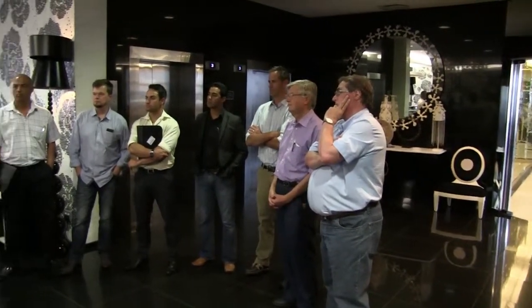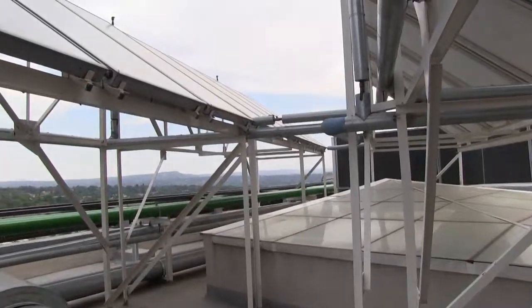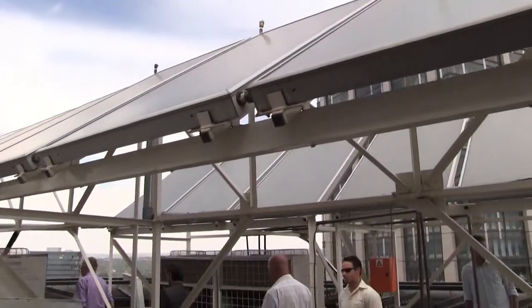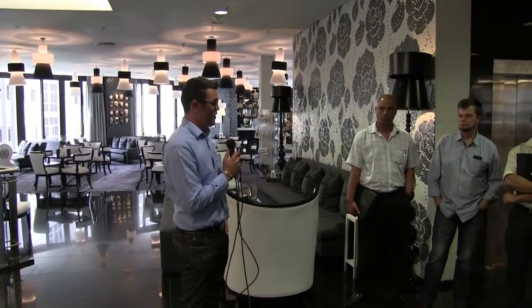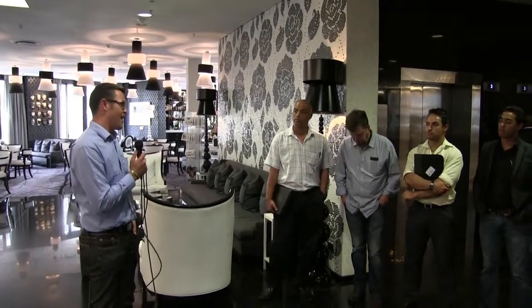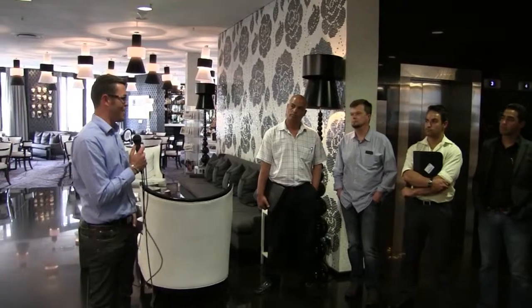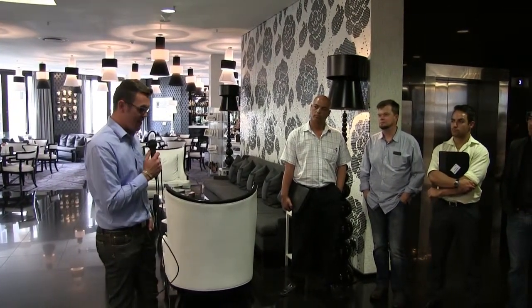The system provides approximately 20,000 liters of hot water per day at a 70% occupancy rate for the hotel, which means approximately 70 liters of hot water per day was specced for each person occupying the hotel, which is at the higher end of general industry standards for how many liters of hot water persons use per day.